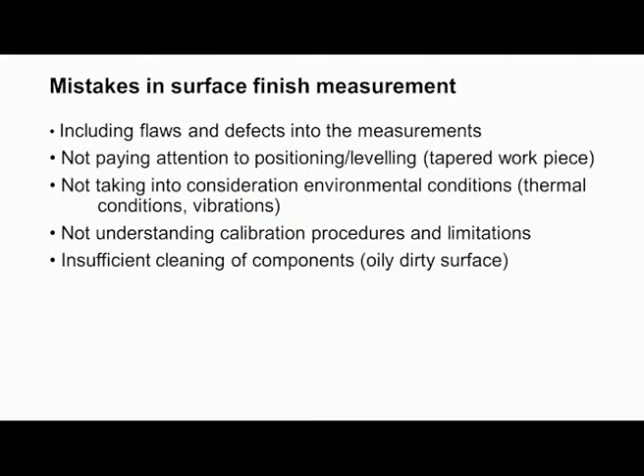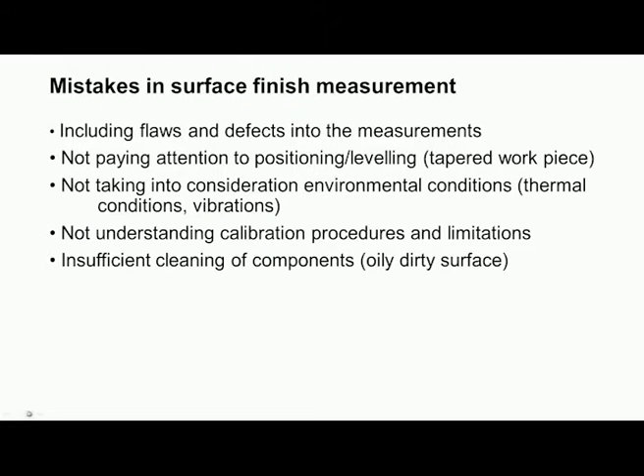Now let us see what are the common mistakes made during surface finish measurement. As per the standard, we should not include the flaws during measurement of the surface. Say for example, we have a surface like this, and somewhere here there is a flaw, like maybe a burr or a crack or a blowhole. Initially we should check the surface visually. If necessary, we should use a magnifying lens and check the surface. If there are surface flaws like this, such an area should not be used for assessing the surface roughness. We should select a surface where no visible surface defects are present. If we include the flaws, then we get some result which will not be useful.